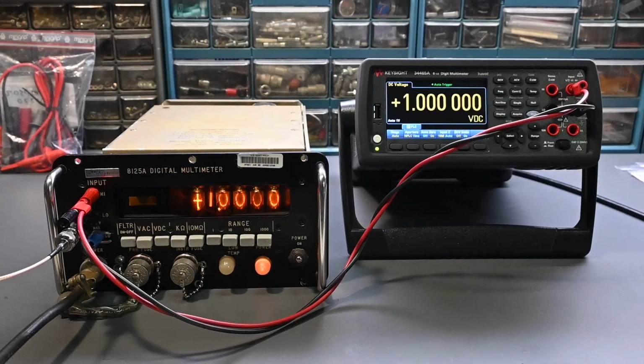All right, so I installed the metal shields in the Fluke 8125A, and then I completed the calibration procedure just as it's listed in the service manual. And I have to say I'm extremely happy with the results. So this multimeter is looking spot on. It's very, very accurate. So I'll go through a couple measurement examples and you can see how things turned out.